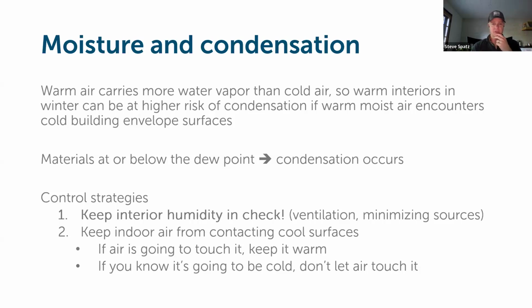And if it's accumulating to a high potential and there's not a pathway for drying and there's nothing in place to keep that moisture loading from continuing, materials, and especially modern materials, engineered lumber, can start to break down. And that is a critical key point to be preventing through design and then through mechanical systems. So really there's a couple key takeaways from this that simplify it, is that really two control strategies to deal with this is making sure we do keep that relative humidity in that happy range within the building for the occupants and then for the building components itself. And then if you are going to be having air with moisture-laden warm air in the building coming in contact with surfaces, you want to make sure that those surfaces are not cold and below the dew point.